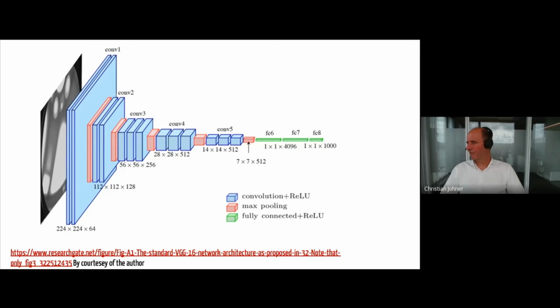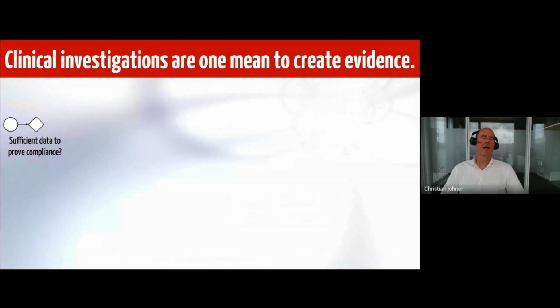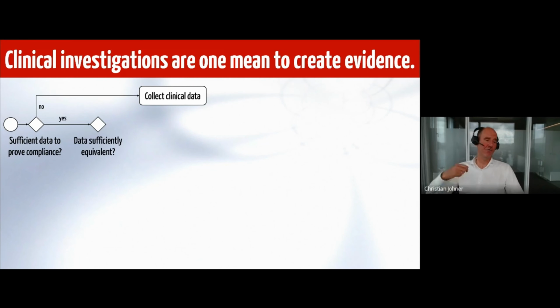Joko was asking me to give a short rundown: when do we need a clinical investigation? And my hint would be the following. What you always have to have is obviously clinical data. And if you do not have enough clinical data, you obviously have to collect this data. If you have enough clinical data, then you should decide whether they are sufficiently equivalent. If not, you again have to collect it, and only if you have enough clinical data can you evaluate this data and decide whether your product is safe, performant, and actually reaches the intended use.